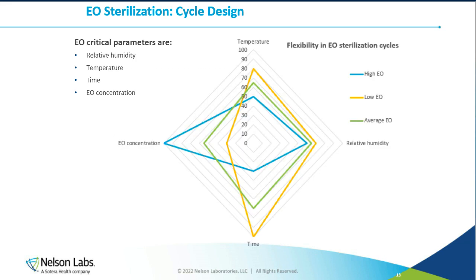Ethylene oxide sterilization basically has 4 major critical parameters. We have, of course, the EO concentration, which is playing a key role. The chemical reaction takes time, so the exposure time is also one of the critical parameters. As I said previously, temperature is probably one of the most important elements to consider. And relative humidity is also one of the 4 pillars dictating the EO sterilization efficacy.